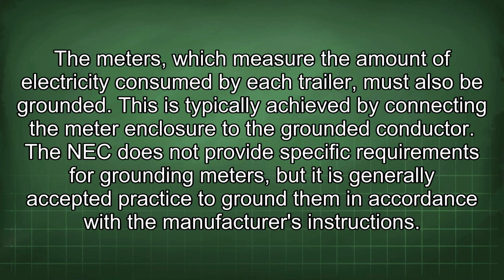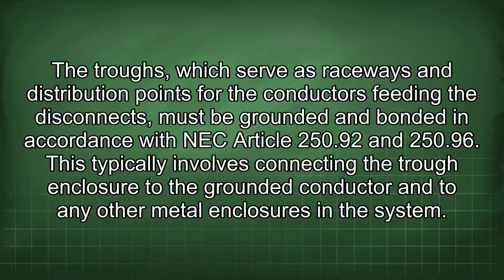The meters, which measure the amount of electricity consumed by each trailer, must also be grounded. This is typically achieved by connecting the meter enclosure to the grounded conductor. The NEC does not provide specific requirements for grounding meters, but it is generally accepted practice to ground them in accordance with the manufacturer's instructions. The troughs, which serve as raceways and distribution points for the conductors feeding the disconnects, must be grounded and bonded in accordance with NEC Article 250.92 and 250.96. This typically involves connecting the trough enclosure to the grounded conductor and to any other metal enclosures in the system.